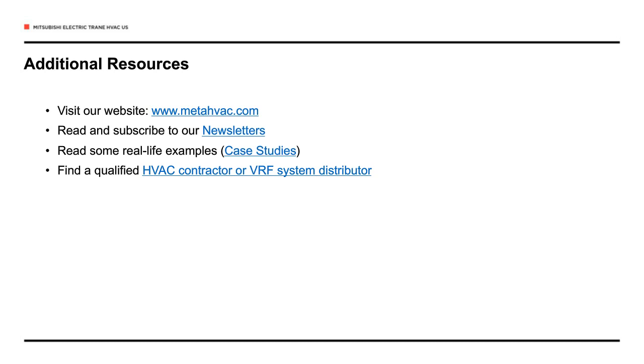All right, next question. What is the max number of devices for each branch box? Well, we talked a little bit about the branch circuit controller, I assume is what the question is going to. You actually have a main branch circuit controller, and you can connect multiple sub-BC controllers to the main BC controller. And one of the interesting things about our latest generation of product is the line lengths have increased by over 130 feet that you're able to run the piping from the flooring. Mike, I don't know if you want to add anything on that.